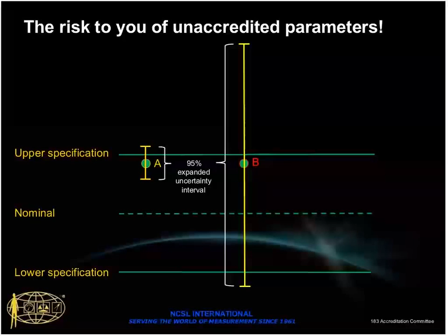It could be anywhere in that yellow interval. If the true answer happens to be in the portions that are shaded in red, then in fact that instrument was observed in specification, but it's really operating out of specification. And so this shows you just how important the measurement uncertainty is. And in fact, I like to make the claim that the actual instrument accuracy that you as a user can depend on is really only as good as the expanded measurement uncertainty of the last calibration. So it has to be measured, and it depends on the actual measurement uncertainty.